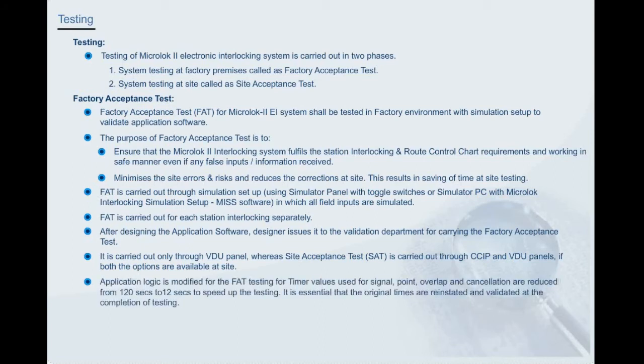Application logic is modified for the factory acceptance test. Testing for timer values used for signal, point, overlap and cancellation are reduced from 120 seconds to 12 secs to speed up the testing. It is essential that the original times are reinstated and validated at the completion of testing.